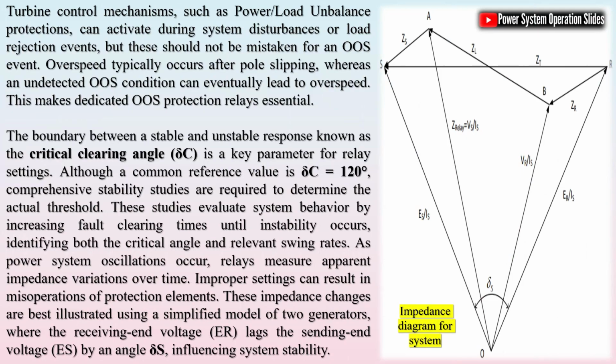Various geometric forms like double blinders or concentric polygons are used for these boundaries, carefully positioned such that the inner boundary lies outside the largest protection region and the outer boundary is sufficiently removed from heavy load areas to avoid false triggers.